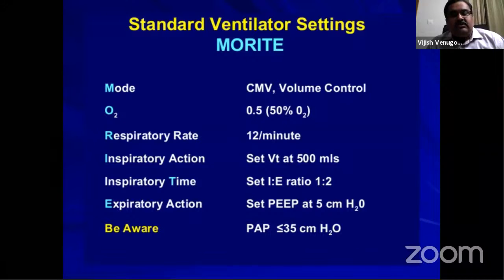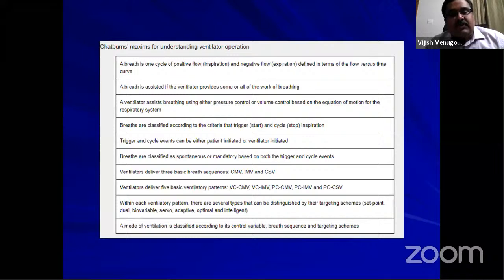So you can set the mode, you can set the FiO2, the respiratory rate, you can set the tidal volume based on the predicted body weight, set the inspiratory time and the expiratory time, and you can set a PEEP. But you should always be aware that the peak inspiratory pressure should always be less. The plateau pressure should be set to less than 28 and the driving pressure should be less than 15 centimeters of water. So Chatburn's maxims for understanding ventilator operation, there are 10 maxims and these are available in standard textbooks.